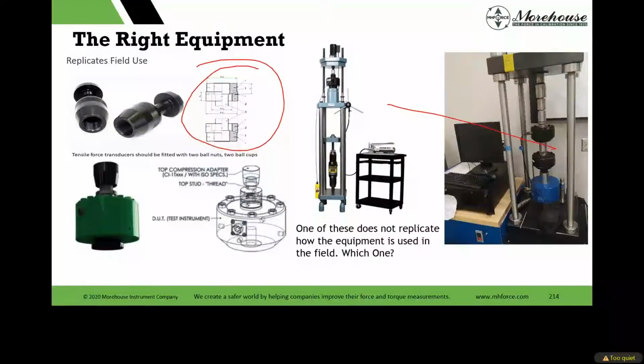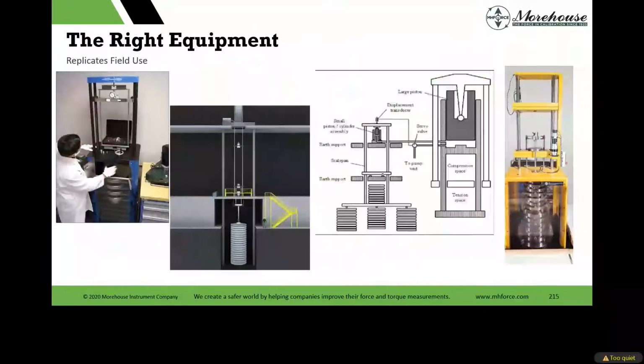This machine really doesn't replicate field use if you do compression and tension in the same setup. In fact, ISO 376 says that they should be separate setups. Most machines, there's a separate setup for tension and compression. It can replicate field use, but you have to unscrew this and make a different compression setup, which, guess what? Most people don't do.